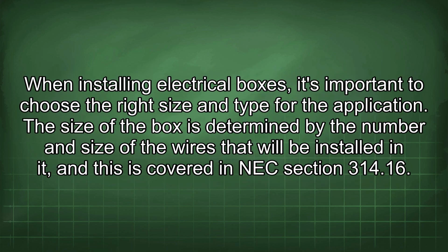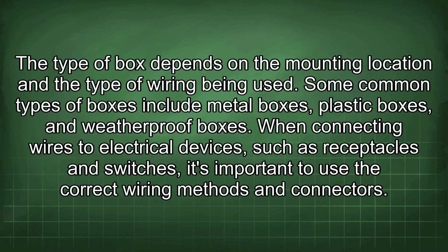When installing electrical boxes, it's important to choose the right size and type for the application. The size of the box is determined by the number and size of the wires that will be installed in it, and this is covered in NEC section 314.16. The type of box depends on the mounting location and the type of wiring being used. Some common types of boxes include metal boxes, plastic boxes, and weatherproof boxes.